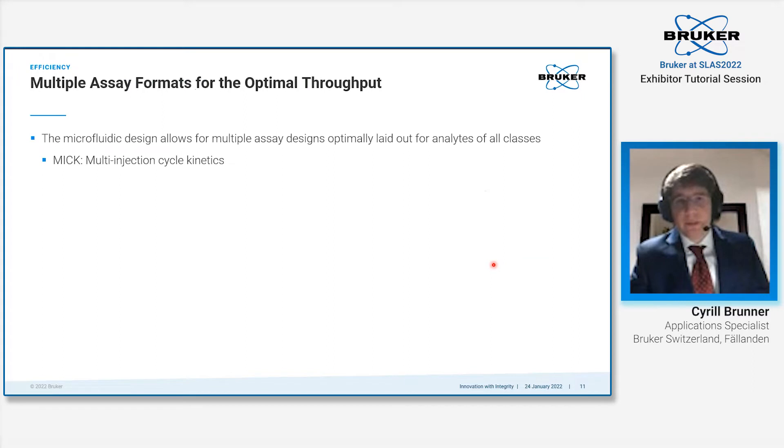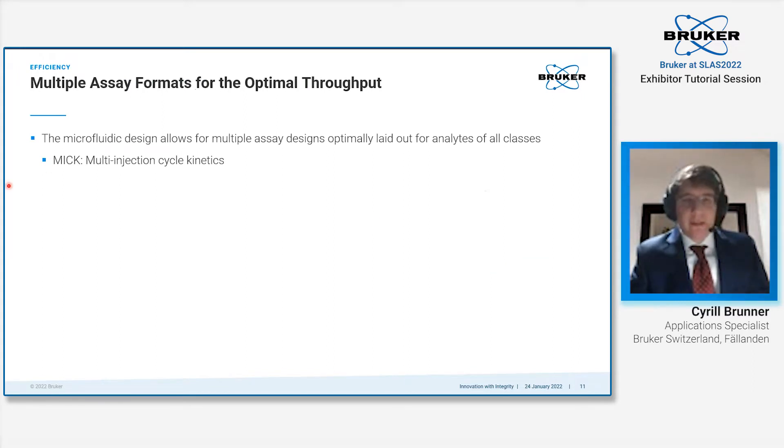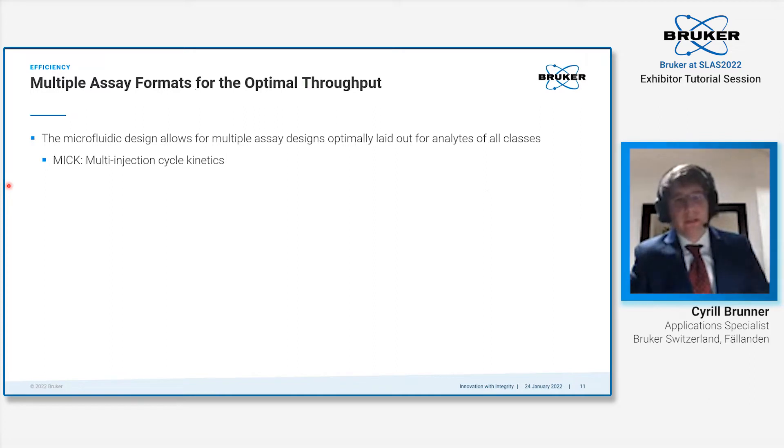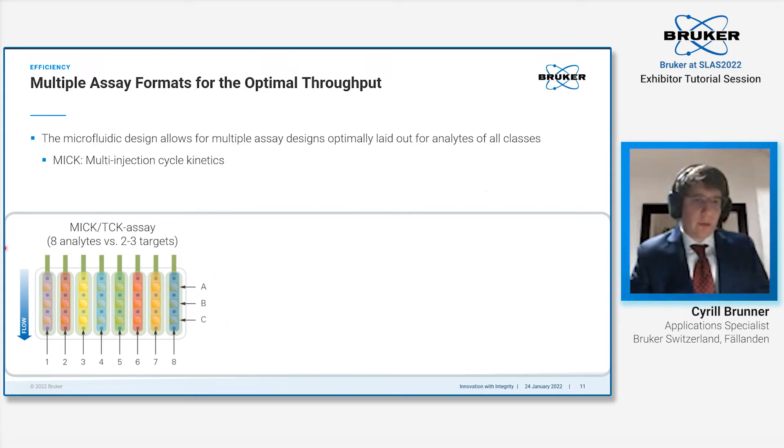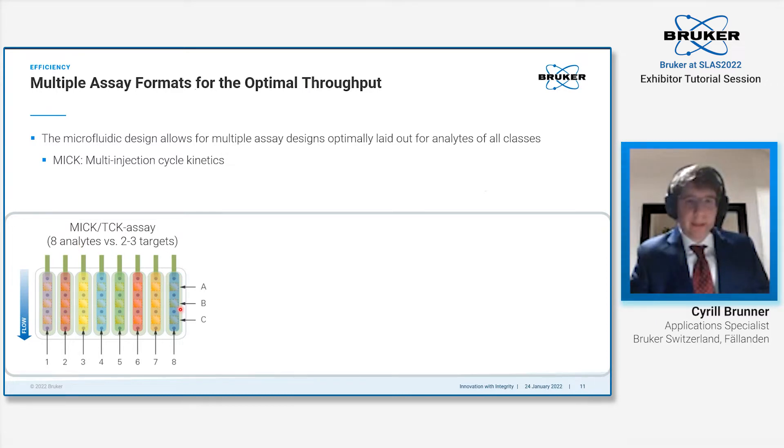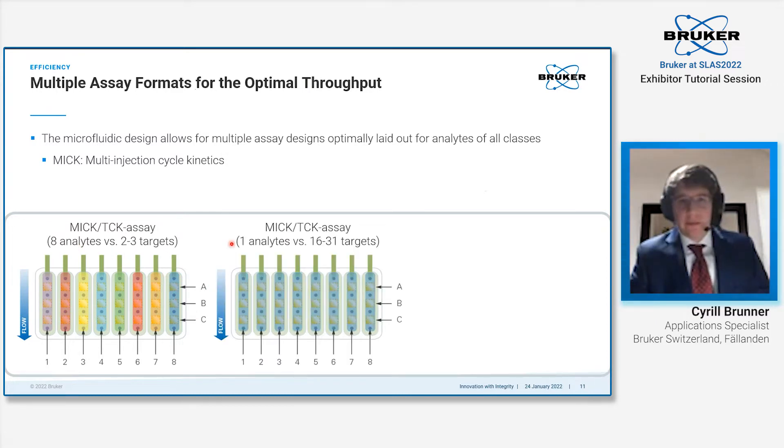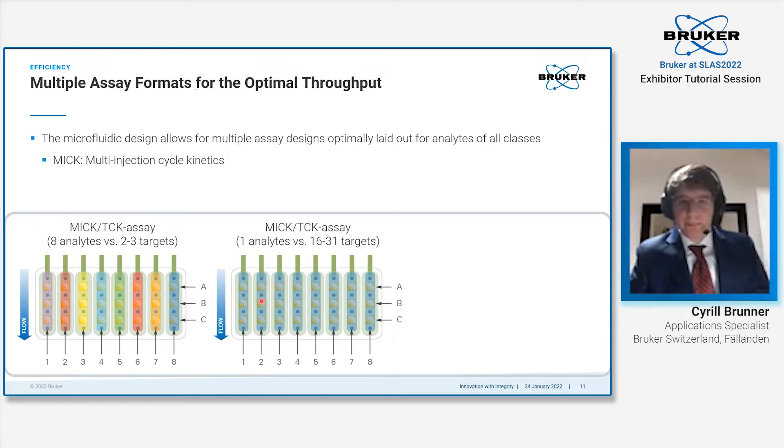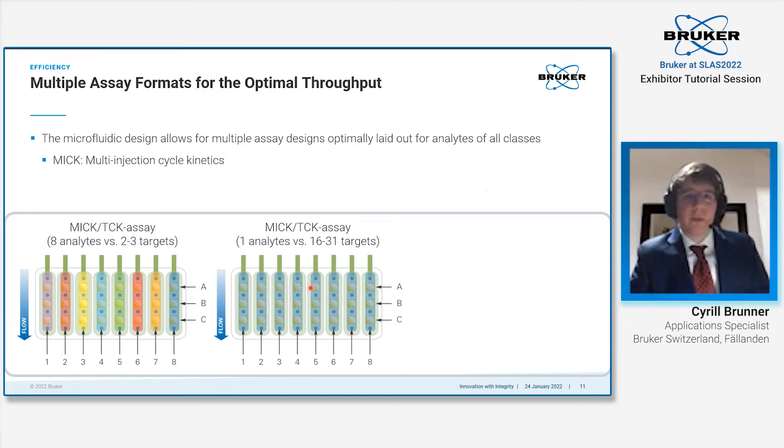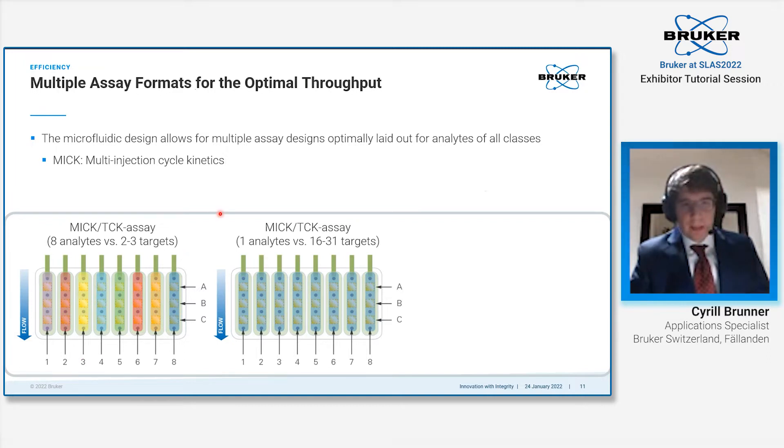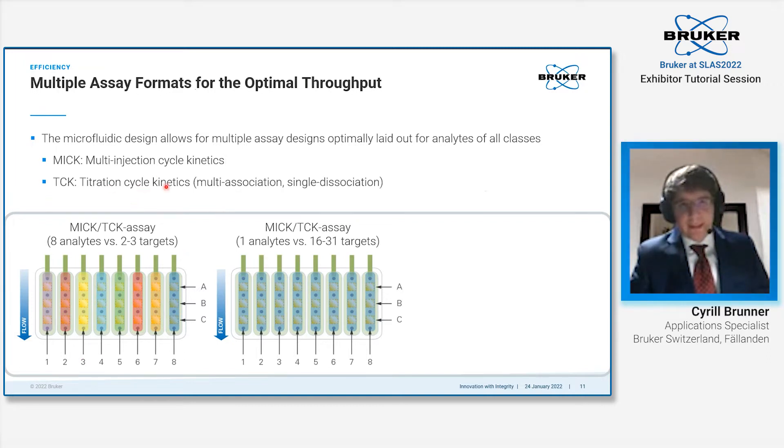There are multiple assay formats which can be done on our system. The classical one would be the multi-injection cycle kinetics, where you make multiple injections of increasing concentration of your analyte. This can be done in two different ways: one way would be with up to eight analytes—each flow channel has a different analyte versus two to three targets. Alternatively, you can bring up to 31 targets on your sensor and inject one analyte. This would be typical for biologics where you have 31 antibodies immobilized by capture approach.